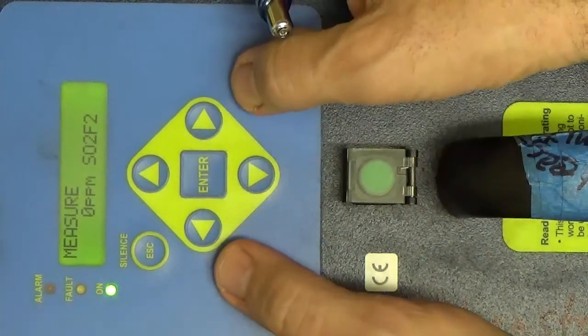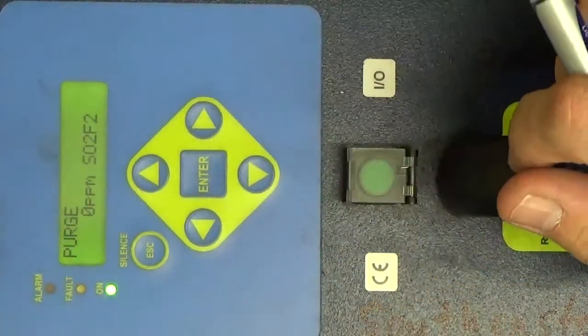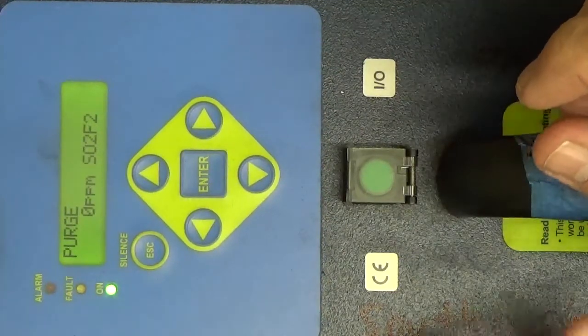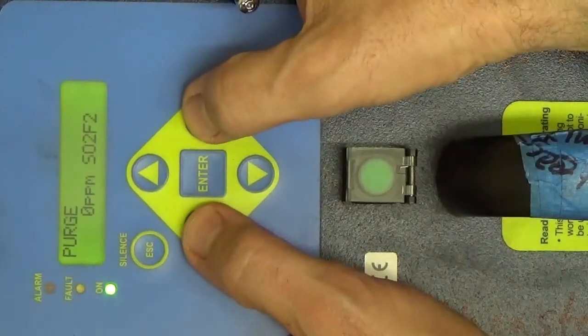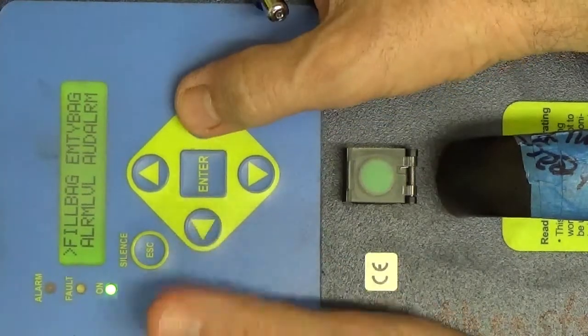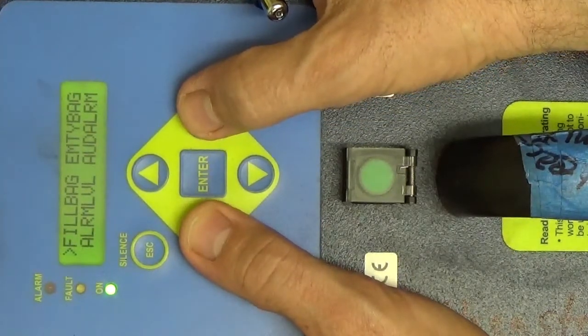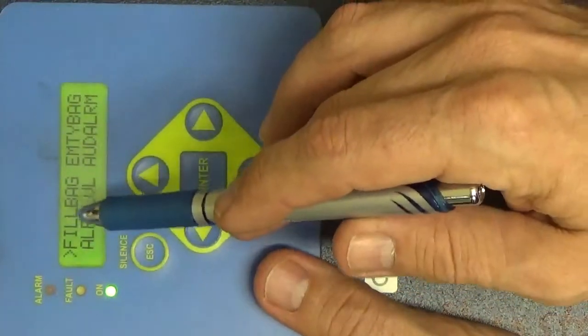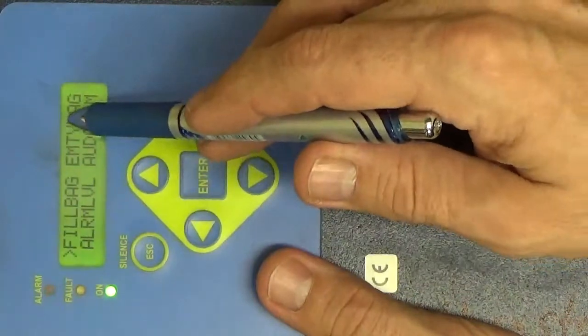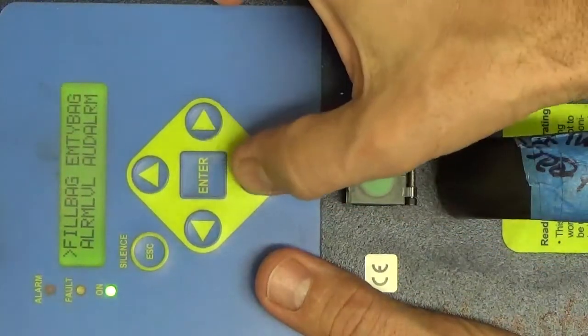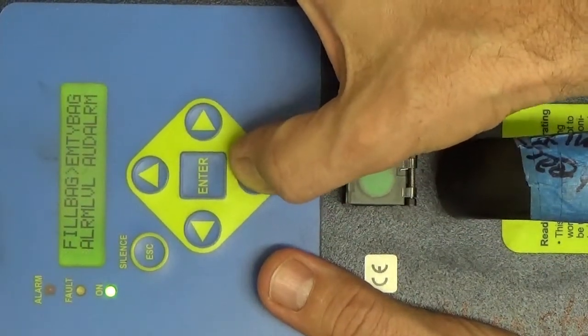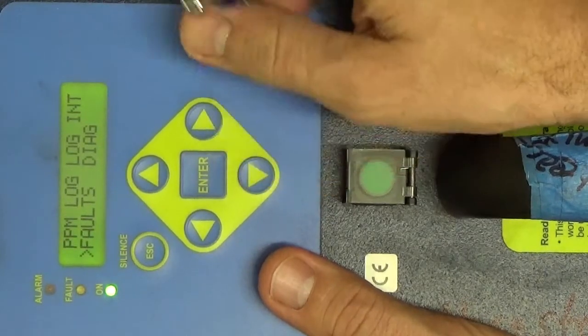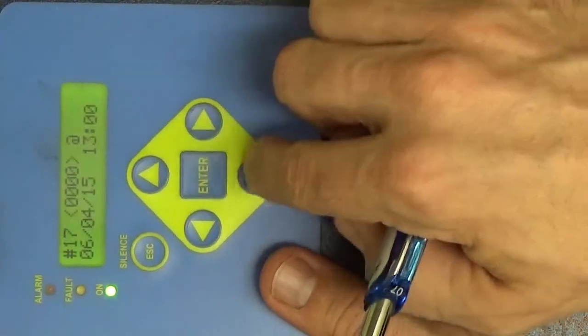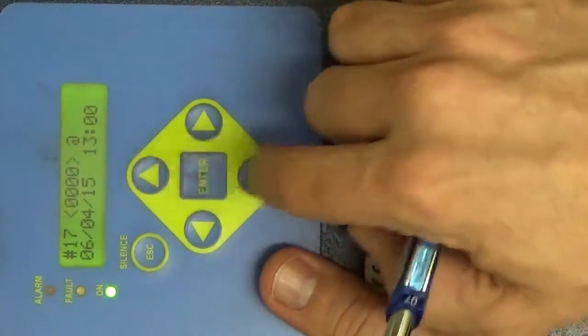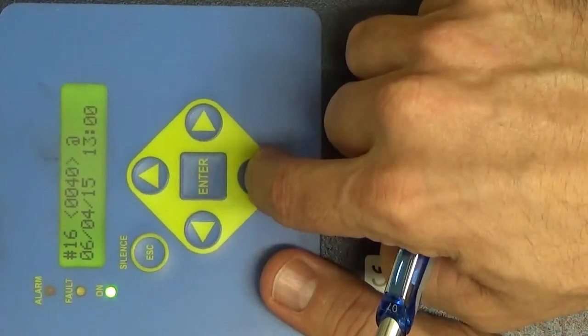Next we're going to go into the internal settings and check things out. So our first level menu, press the right and left arrow buttons together and you'll get to the internal menu. Starts with fill bag, alarm level, empty bag, and we're going to scroll through this list till we get to faults to begin with, and we're just going to go into faults, press the up or down keys and just scan through the faults.